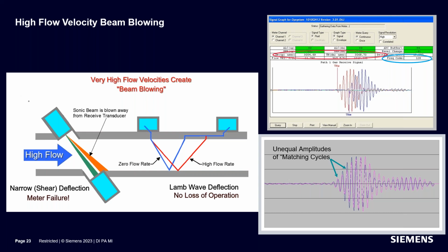And this can throw a flow meter for a loop, because as the beam gets blown, you can get a change in the correlation between the upstream and the downstream, which can cause flow measurement errors. To combat that, Controlotron developed something called beam blowing correlation, or BB core. We've since changed it, and it's now called HF, and it's built into the 230 and the old 1010 meters.